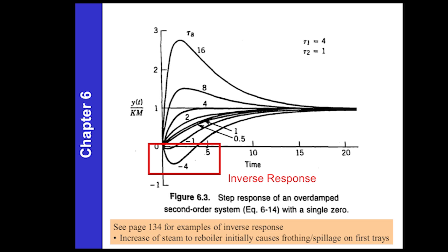One example of an inverse response: as you initially increase the steam to a reboiler, you can have some frothing or spillage on the first trays, which can exhibit this type of inverse response — where you first see the response go down before it goes back up again. That's just one example of an inverse response on a level on some of your trays for a reboiler change — an increase in steam to the reboiler.